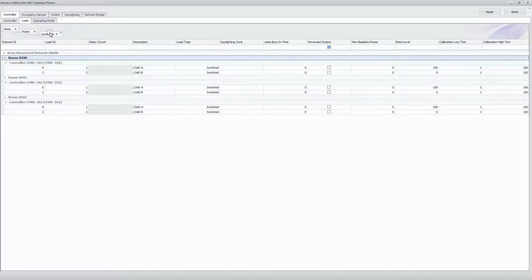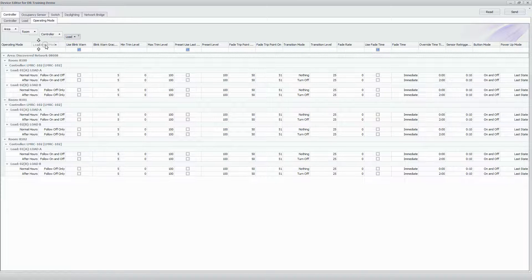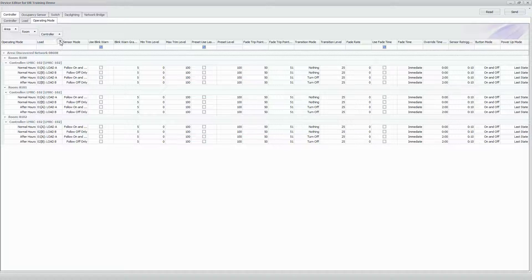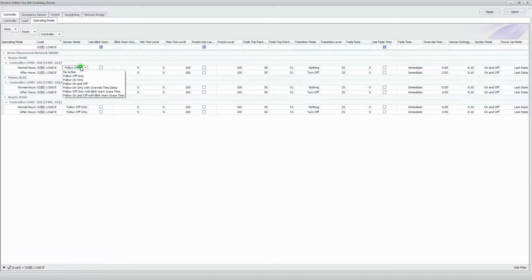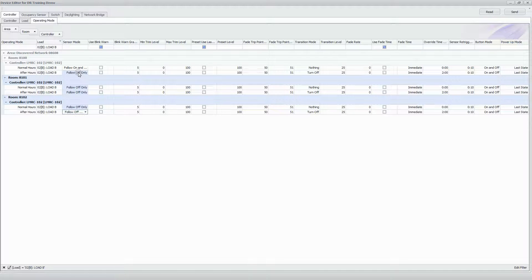The last thing to change is the operating mode. Since this is a shed event example, we're going to change the off-only condition to Follow On and Off on these rooms. The assumption is that you're at 100% lighting and want to go to 50% during a shed event. Filter down to Load B only, change it to Follow On and Off, then Control+C, select down with Shift, and Control+V — applying Follow On and Off to Load B for both normal hours and after hours, however the site needs to be configured.